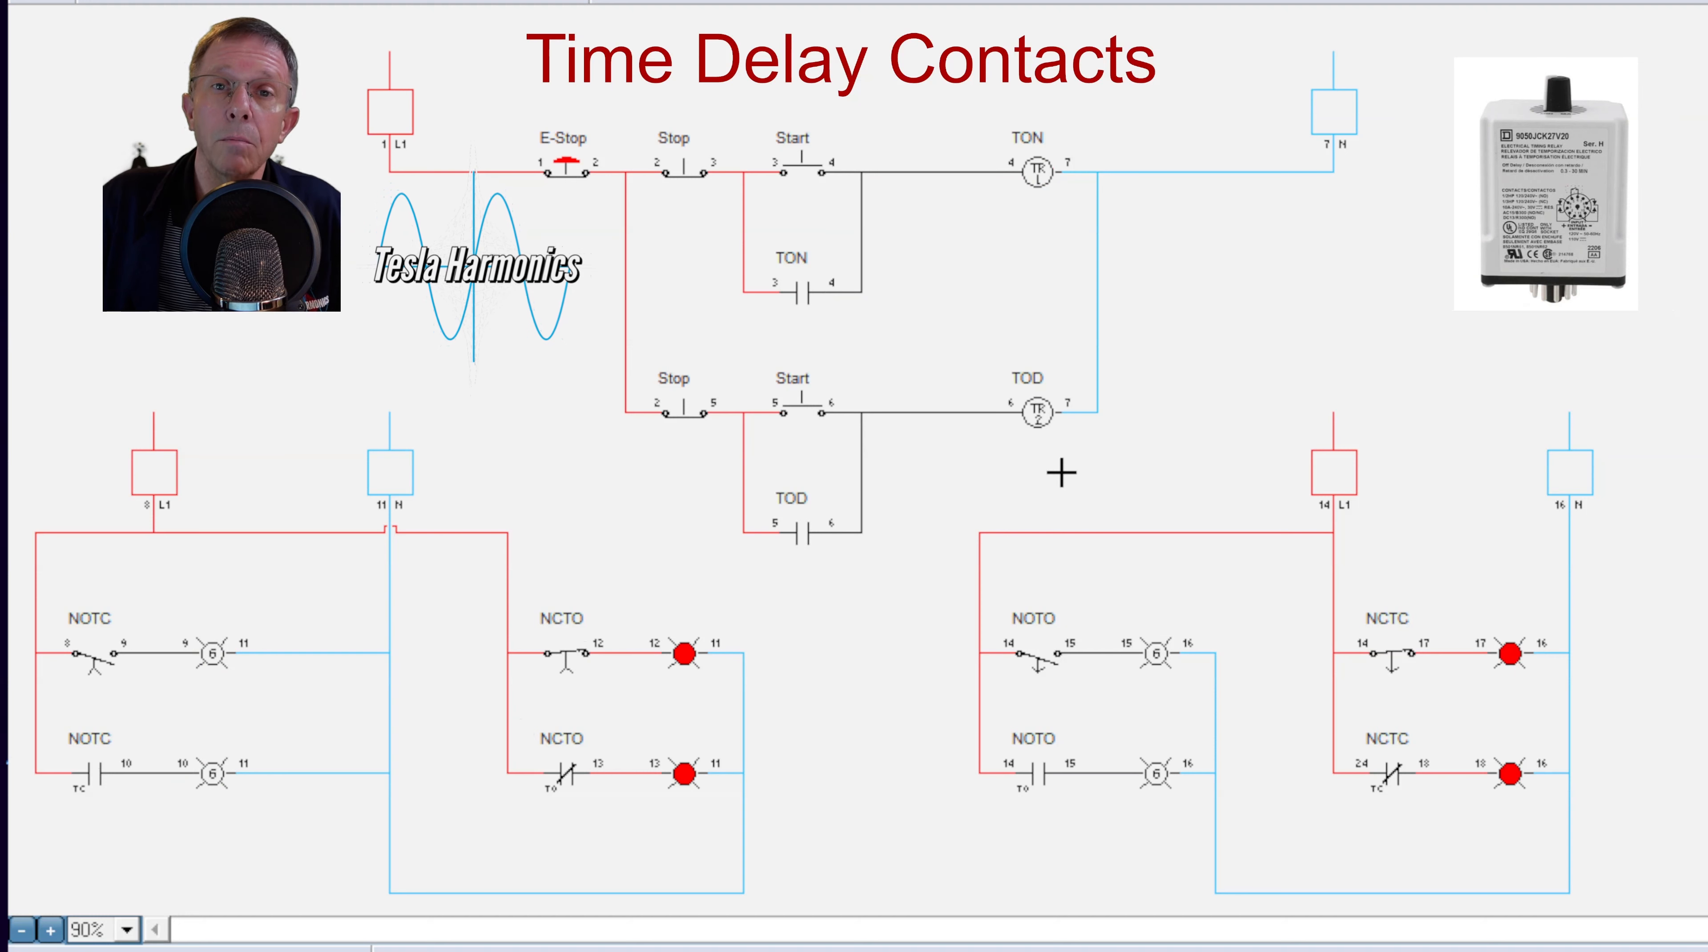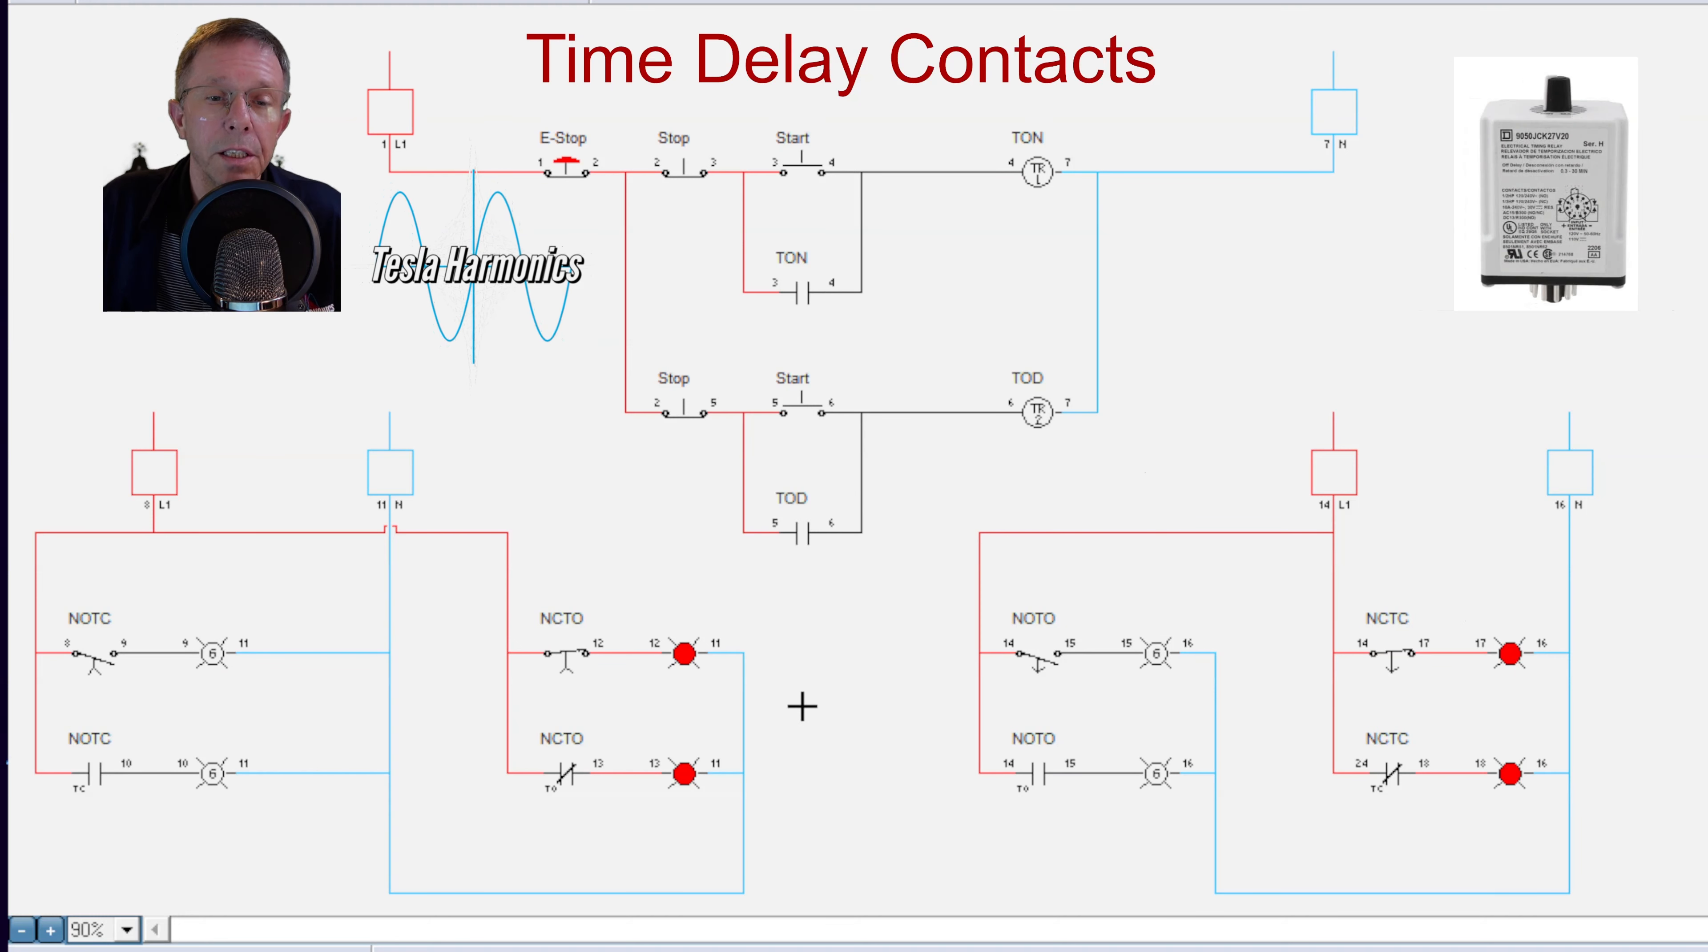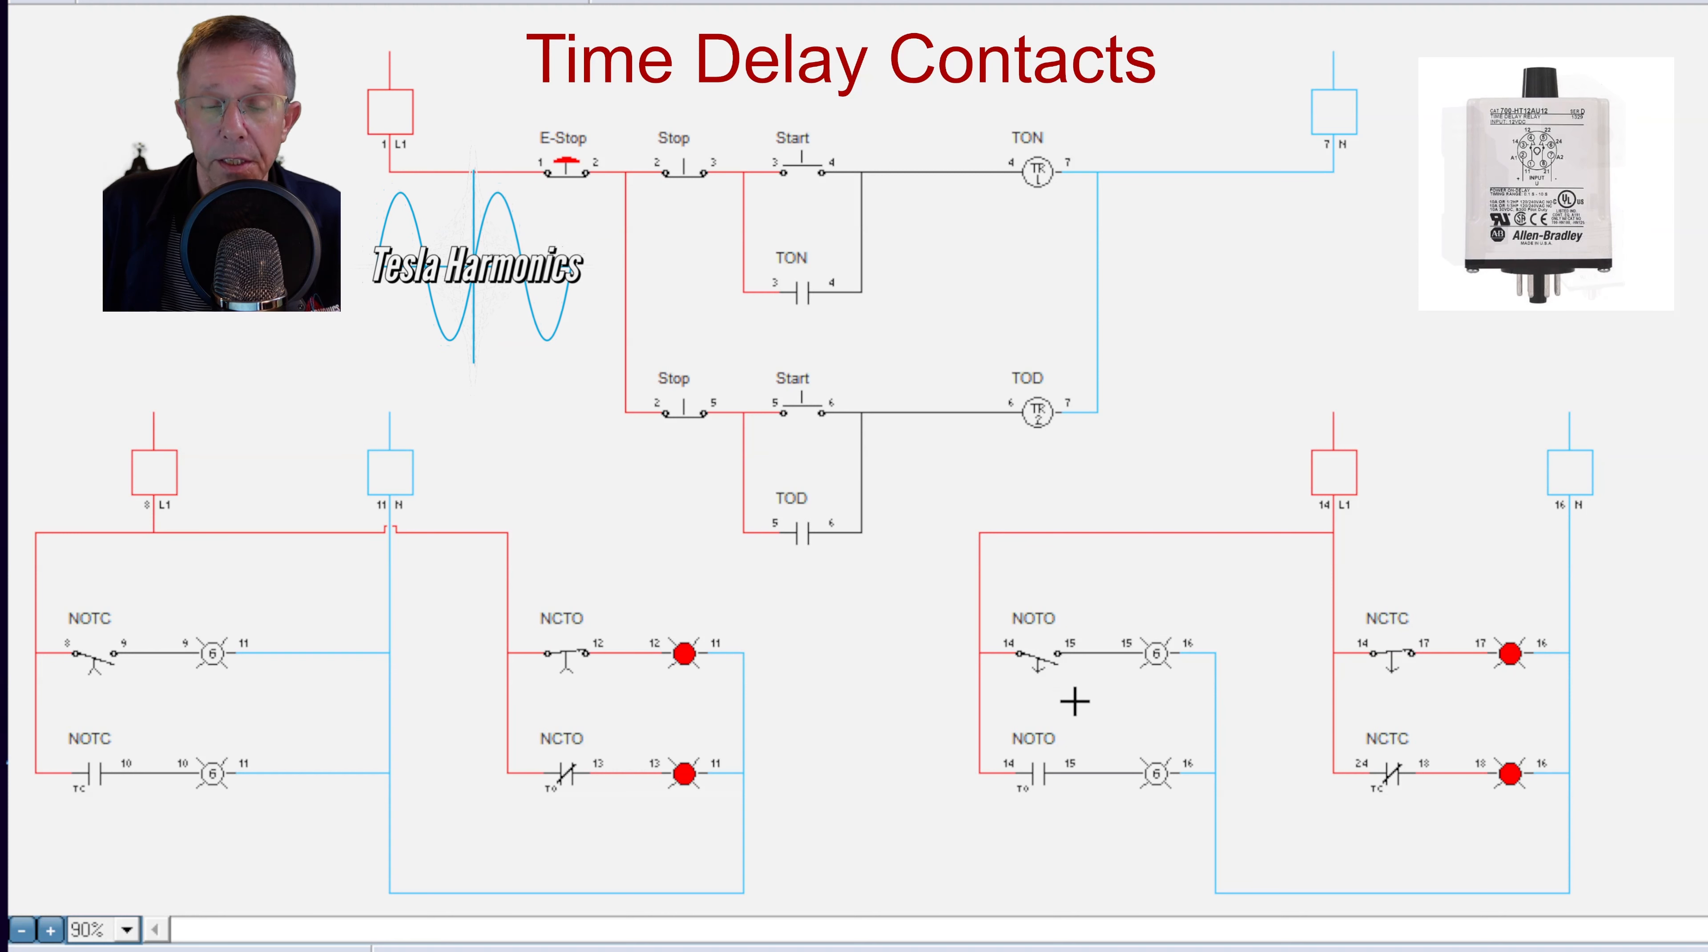Okay, so that's our time on delay. Now if we take a look at the contacts on our time off delay circuit, when I energize that time off delay coil, the two open contacts are going to immediately close because this one has the arrow pointing down. That means that it's going to immediately go the other direction and time to go the direction of the arrow. So it's going to immediately close and turn on the green light.